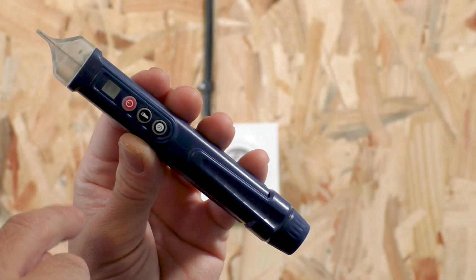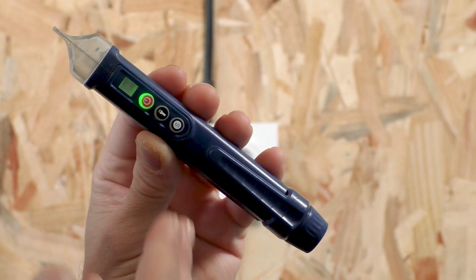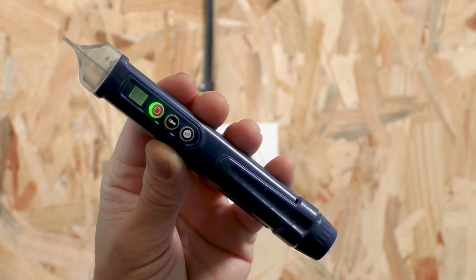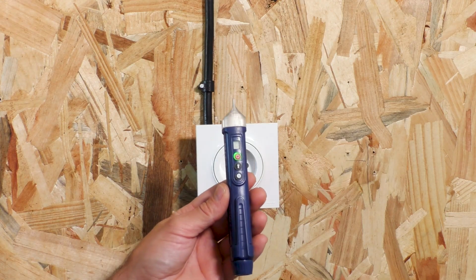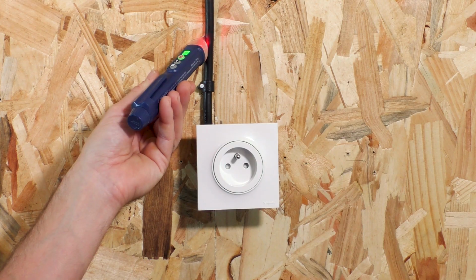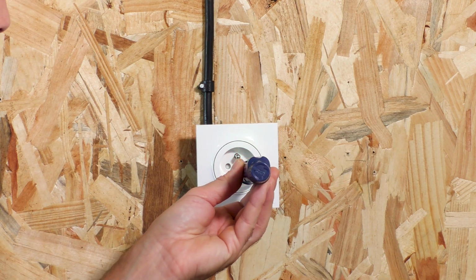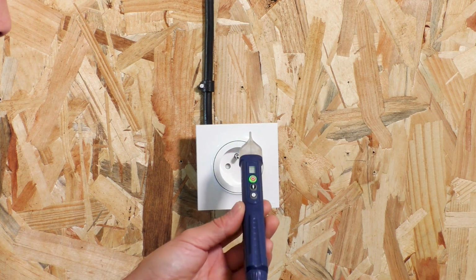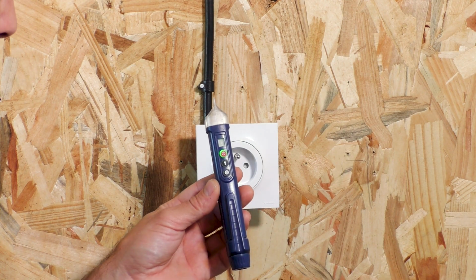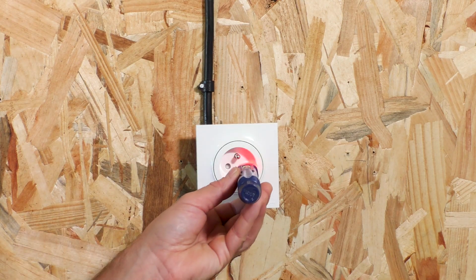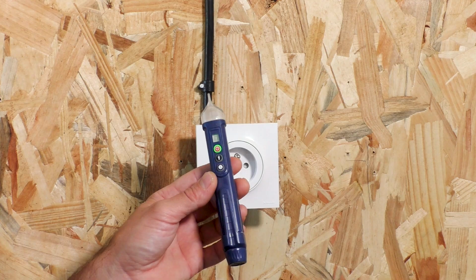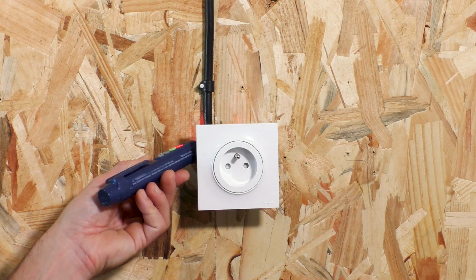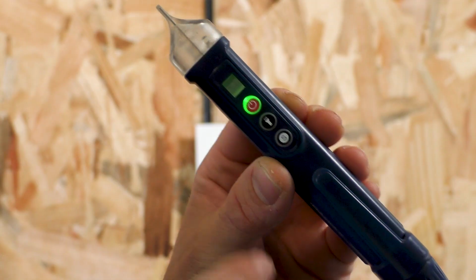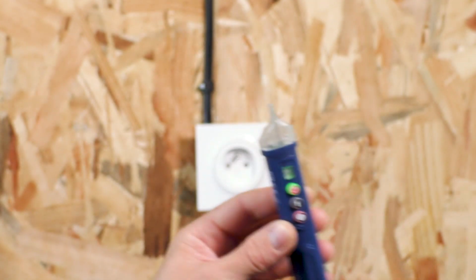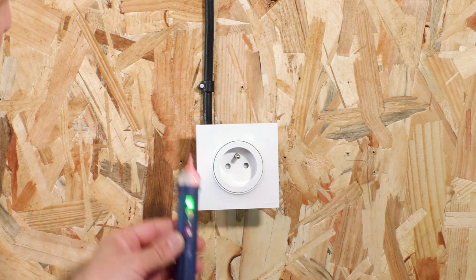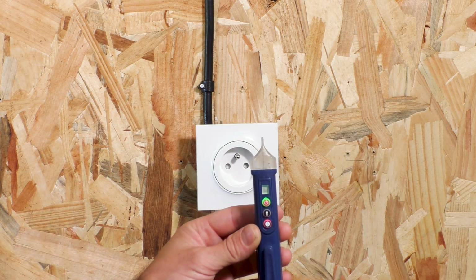This one is a bit safer because you need to actually turn it on to use it. So you immediately see that the batteries are good, reducing the chances of a false negative reading. It starts in a low sensitivity mode, which means it will only react when you put it really close to a live wire. So it lowers the chances of a false positive reading too. It will also beep and blink at different speeds depending how close it is to a live wire. When you press this high sensitivity button, it will react when it's anywhere near an energized part, or even when you slightly move it.